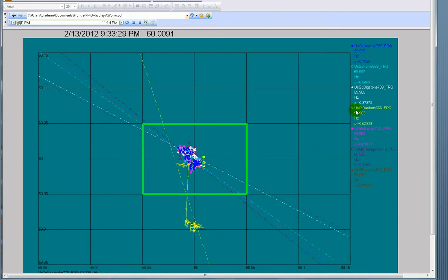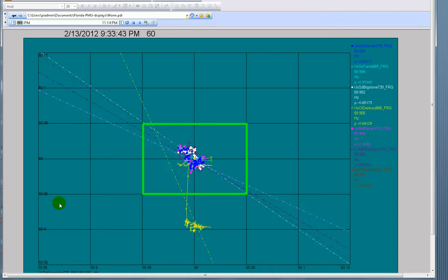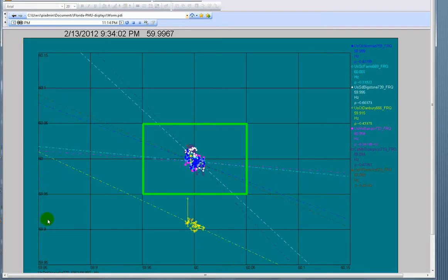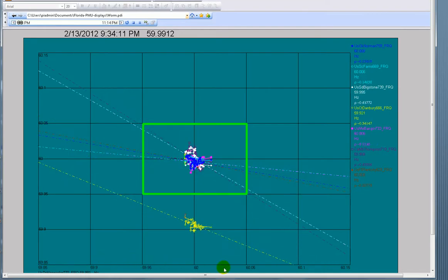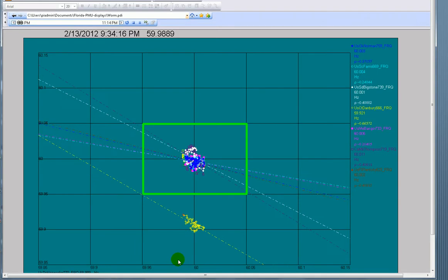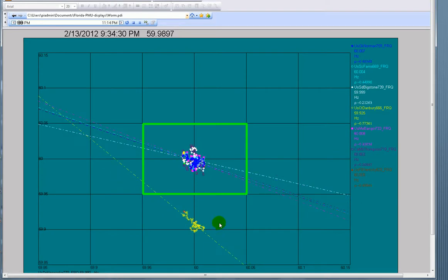This shows that Danbury is operating independent of the rest of the grid. Now the state chart, which we also call a worm chart, is a plot of the frequencies of the stations in the Eastern Interconnection plotted on the y-axis versus the frequency of Knoxville, which is the base station in the interconnection. So you'll see that we have Danbury operating entirely asynchronously from the rest of the grid.